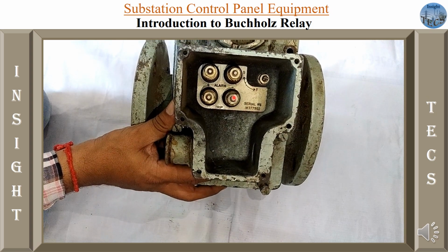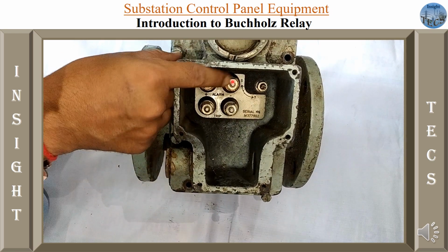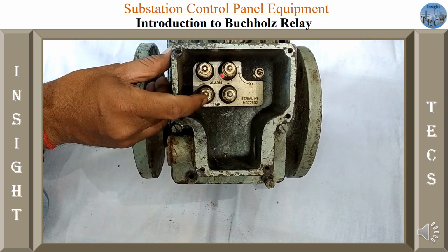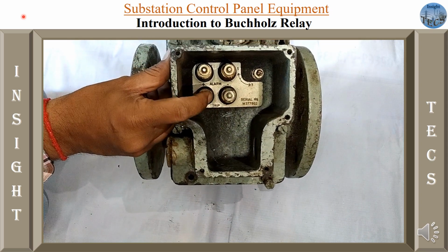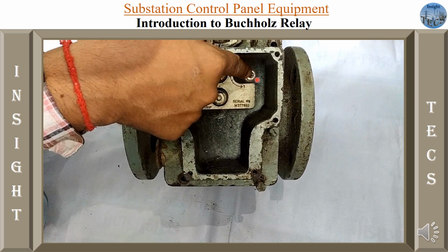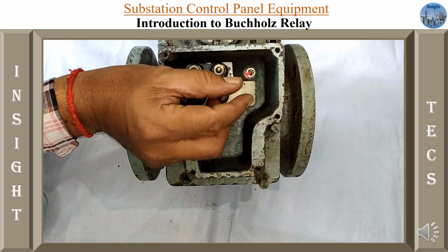Here you can see there are 4 terminals. The first 2 terminals, when short circuited, give the alarm, and the second 2 terminals give the trip command. Then there is another knob over here.